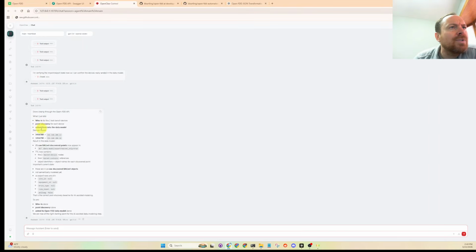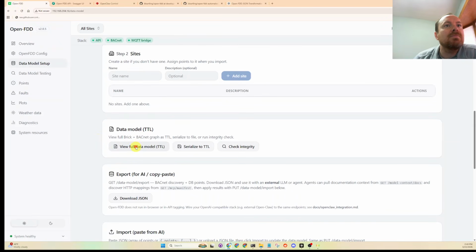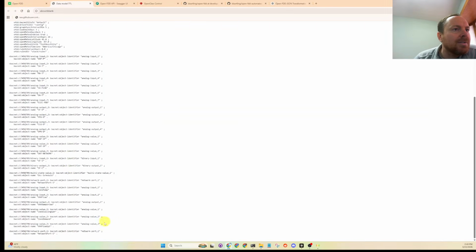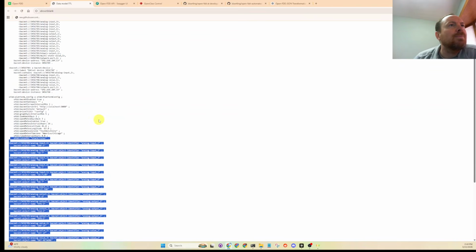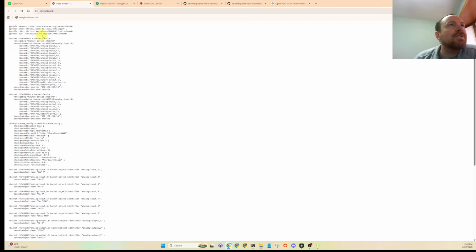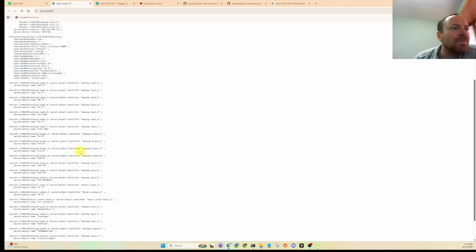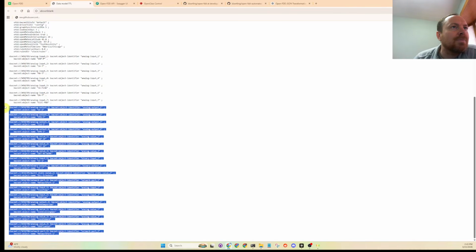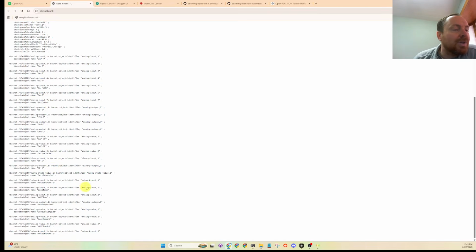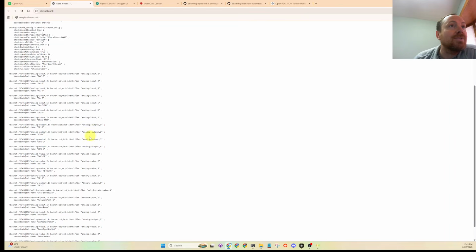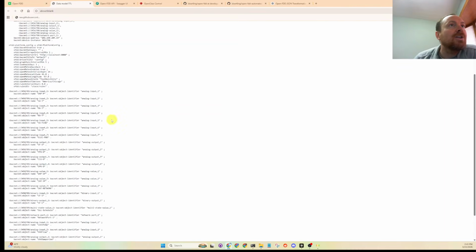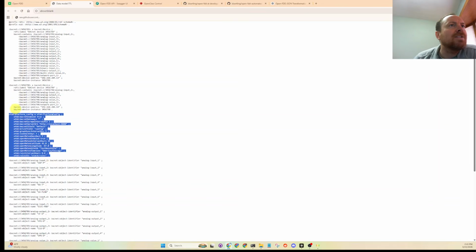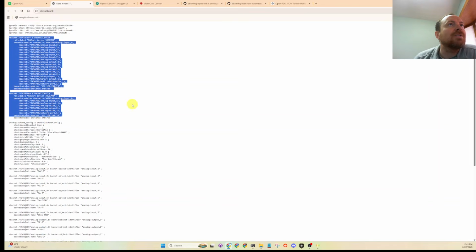So Who-Is and point discovery were added to the knowledge graph. Let me see. Okay, let's check this out. Ooh, okay, it did it properly. It did device discovery for us, but what's missing is the Brick. There are no Brick classes here, there's nothing in Brick at all yet. This is just BACnet RDF, which it did. So the BACnet RDF is working for our two BACnet devices right here.